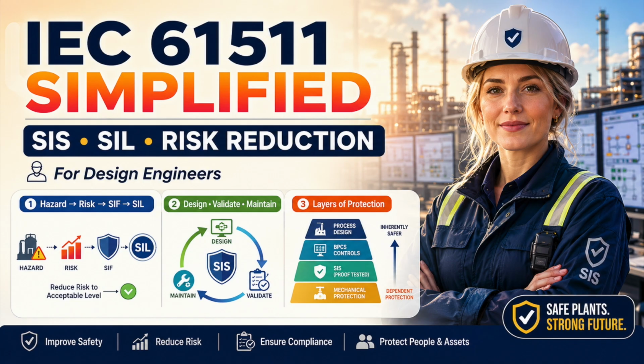This is why competence and accountability matter. Who owns the hazard analysis? Who owns the SIL determination? Who owns the safety requirement specification? Who owns the valve performance? Who owns the proof test strategy? Who owns the bypass? Who owns the modification? Who owns lifecycle performance after handover? When responsibility is distributed without clear accountability, critical assumptions disappear between departments.